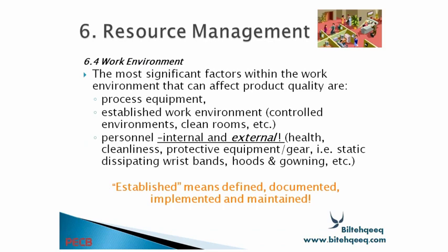Work environment. The most significant factor within the work environment that can affect product quality are process equipment. Establish work environment, controlled environment, clean room, personnel, internal and external, health, cleanliness, protective equipment, gear, static dissipating wrist straps, hoods, and gowning. Established means defined, documented, implemented, and maintained. And you have to establish this work environment. It means that it should be defined, documented, implemented and maintained.